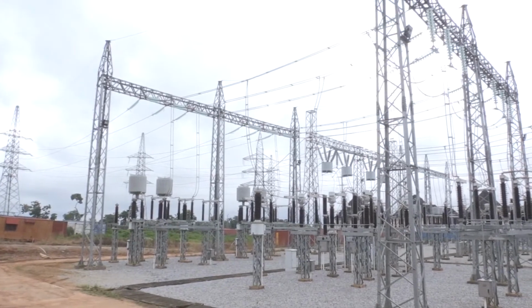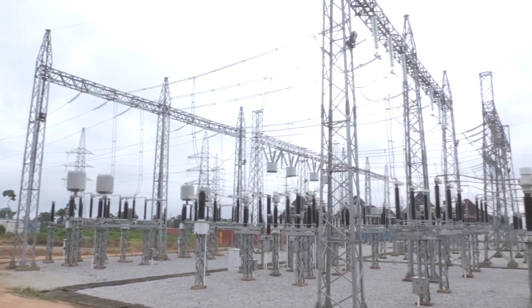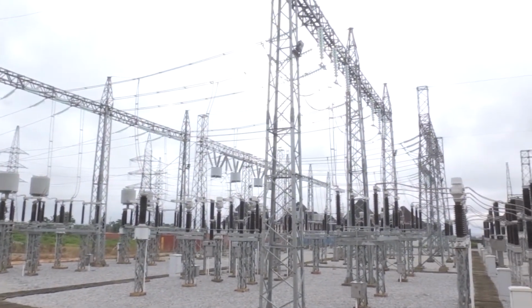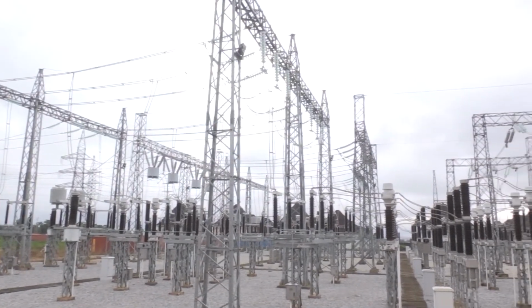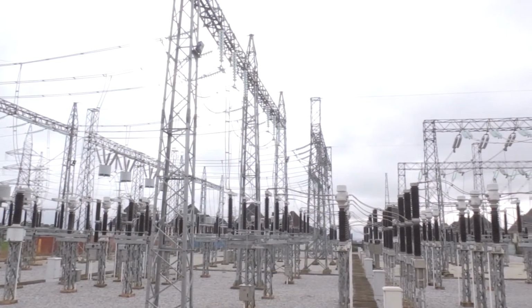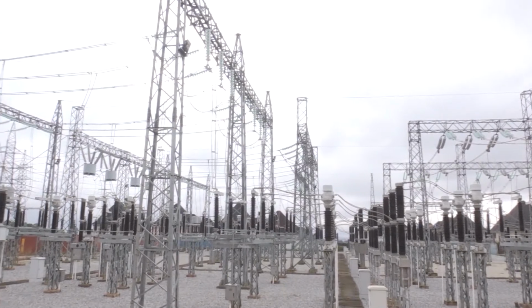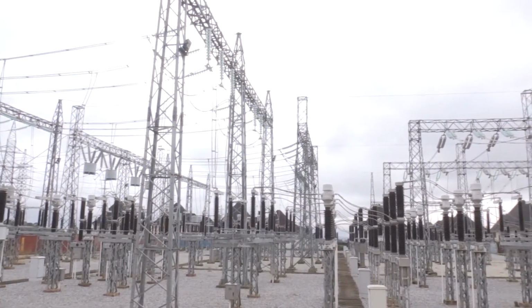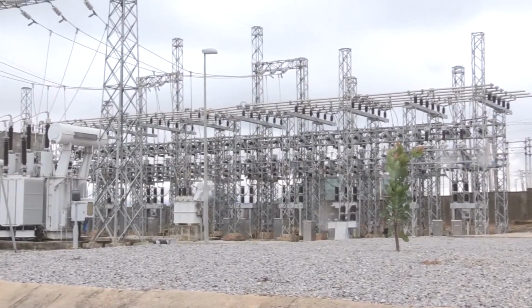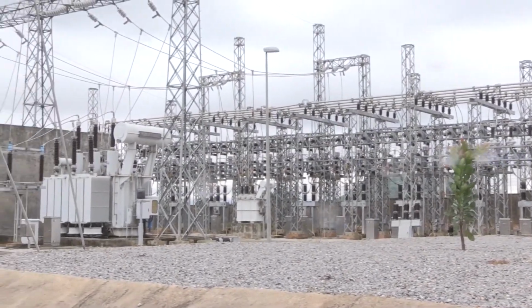The Kokwaba substation is designed to accommodate any expansion needs of the capital city, especially as industrialization activities intensify. It has a span switchyard with space for installing more power transformers, with provision for an additional 2x100 MVA substation.